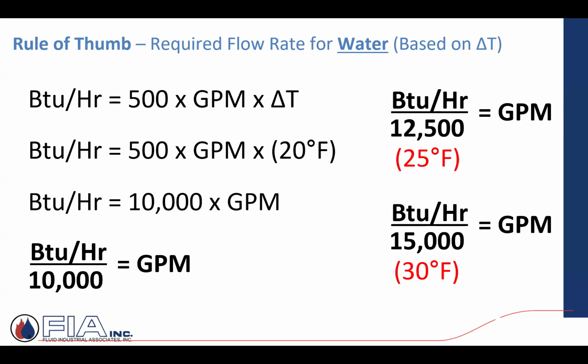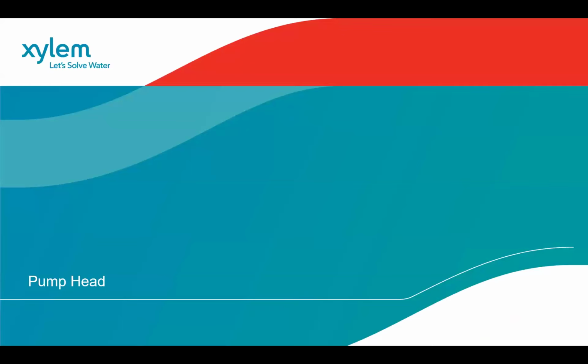Like I said, 20 degrees is very standard, but it's not written in stone. You can design on different delta T's. And as you do, that 10,000 becomes a different number as you just plug in 25 times 500 or 30 times 500. And that will change, because there's an inverse relationship between flow rate and delta T relative to load, BTUs per hour. The higher the delta T, the lower the required flow rate. The tighter the delta T, the higher the flow rate. So it's just in the math. It's just a number, but just get comfortable with it.